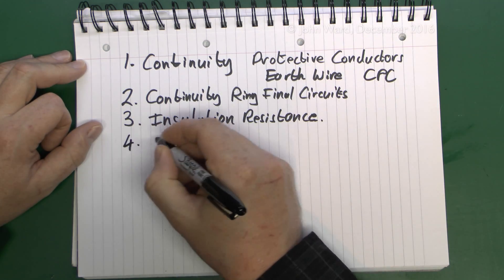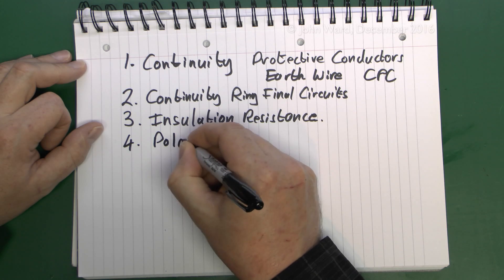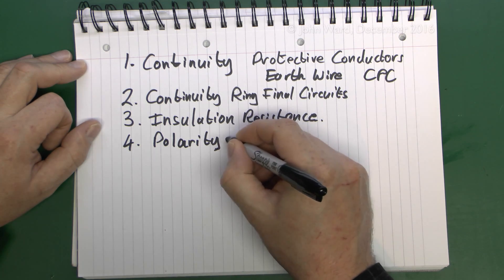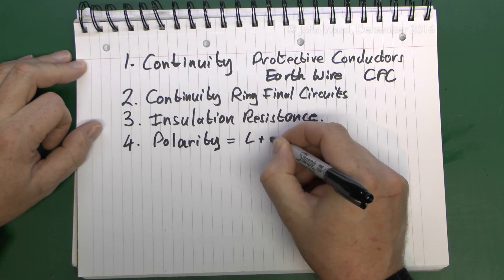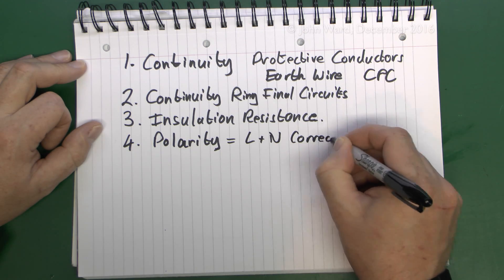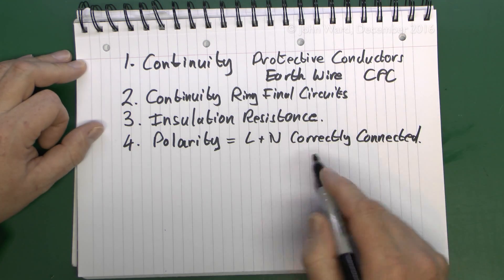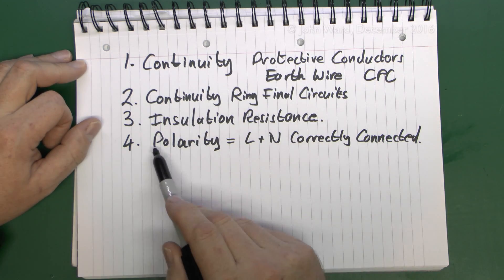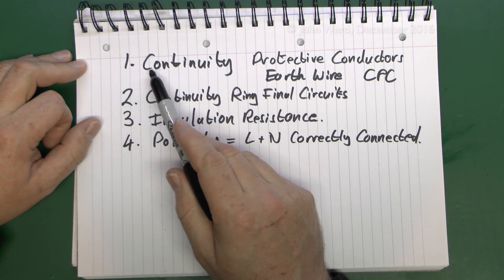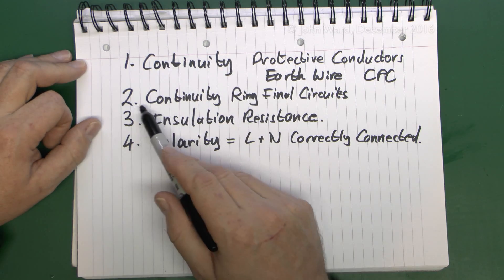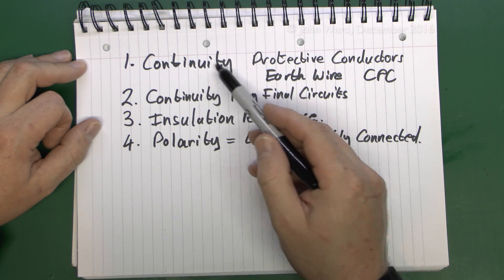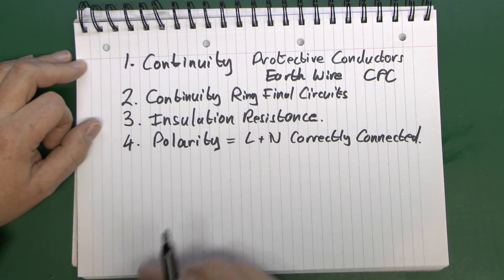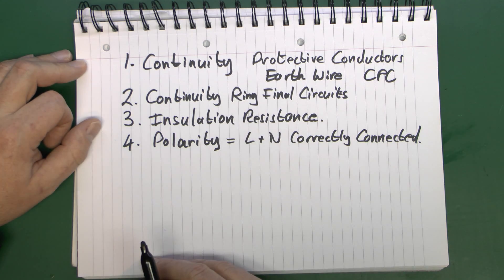Test number four is polarity. AC circuits don't have polarity in terms of negative and positive, but what you're really checking for here is that line and neutral are correctly connected. This needs to be done on all circuits regardless of what type they are. However, it is actually possible to do the polarity test as part of either continuity test one or continuity test two. So if you've done one of those by the most common methods, it's fairly likely you've already done this. But in any case, it does need to be done on all circuits.